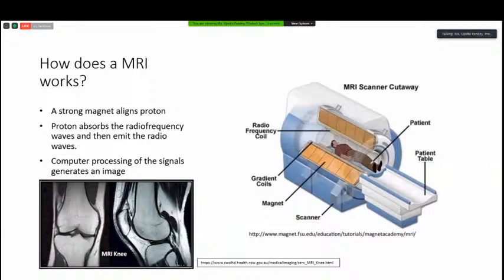And when the radio frequency coil is turned on, the unmatched protons absorb the energy of the RF wave, which causes them to flip on their axis. They are still in line with the magnetic field, but now they are in the opposite direction. So when the RF pulse stops, the protons release the energy and return to their previous alignment, emitting a signal back to the coil. That signal turns into electric current that the scanner digitizes. The scanner processes the signal using advanced algorithms in order to produce the image.